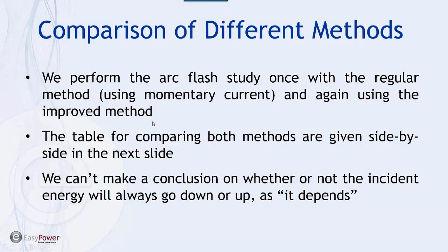Comparison of the different methods. Now, we performed the arc flash study once with the regular method using momentary current and again using the improved method, or integrated method. The table comparing both methods is given side by side in the next slide. We can't make a conclusion on whether or not the incident energy will always go down or up, as it depends.